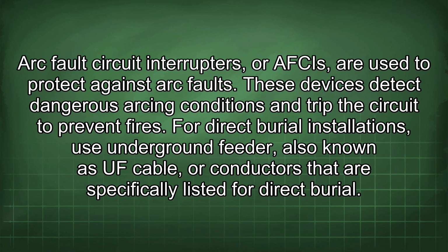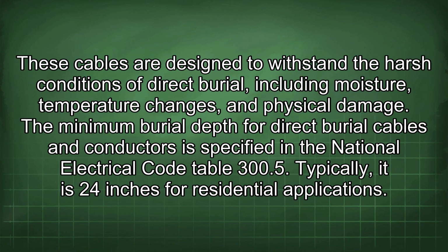For direct burial installations, use underground feeder, also known as UF cable, or conductors that are specifically listed for direct burial. These cables are designed to withstand the harsh conditions of direct burial, including moisture, temperature changes, and physical damage. The minimum burial depth for direct burial cables and conductors is specified in the National Electrical Code Table 300.5. Typically, it is 24 inches for residential applications.